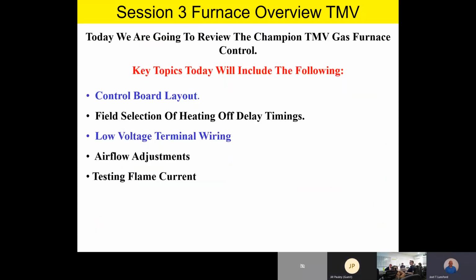So some of the key things we're going to be talking about specifically is control board layout like we've done before. We're going to literally go over every input and every output on the board. We're going to talk about field selection of heating off delay timings, low voltage terminal wiring, airflow adjustment, and then at the end we'll do testing flame current again. Now I know we've done testing flame current at the end of every one of our sessions, but I think it's one of those subjects that's kind of timeless, if you will, in the fact that it's always good to review testing that flame current.